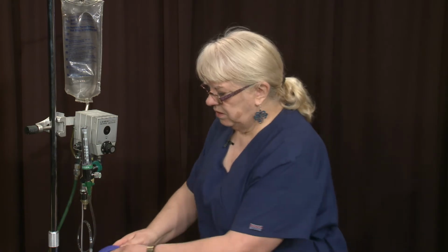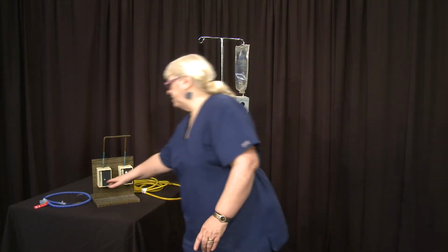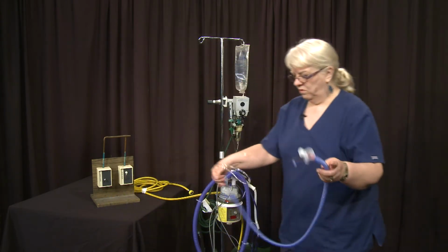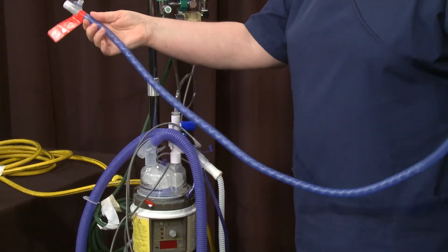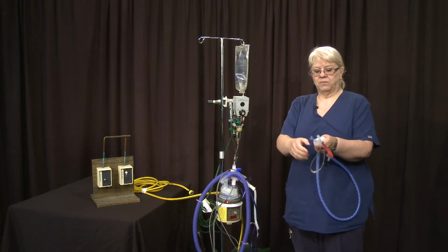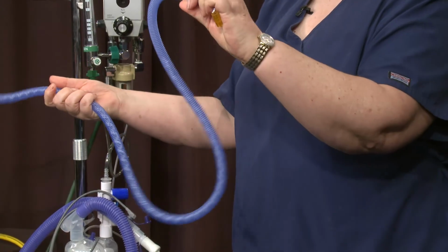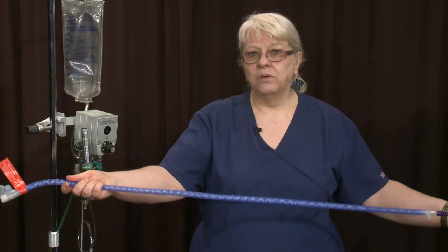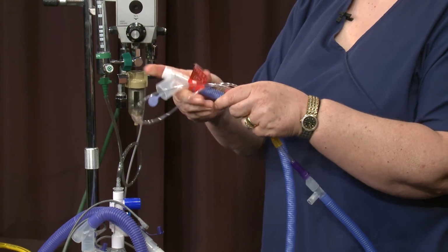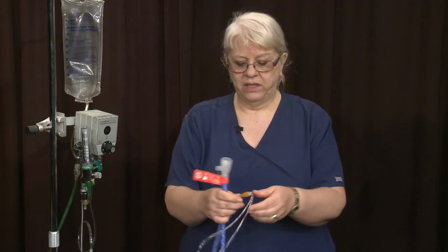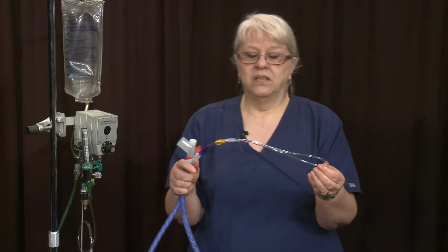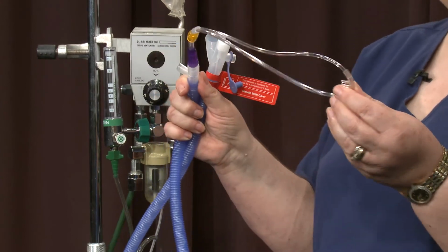Now, if I step over here a minute and pick up this circuit, this is for an infant, or a slightly larger one could be for a pediatric patient. And you can see I've got pretty much the same setup. I've got a proximal, and I've got a distal probe, and this again is for the servo loop. I've still got an attachment back here for my heated wires to prevent rainout. And then the only difference is really up here at the patient, we have different size cannulas. We have 3 sizes, one for preemies, one for neonates, and one for peds. And those, we can choose the appropriate size for the patient.